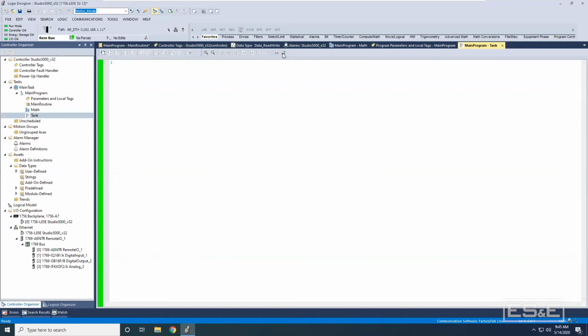But the other thing I really want to highlight is you have the ability to come up to here and you can see this toggle inline view or value display. So we're going to turn that on. I would always recommend adding that. What this does is it now allows you to see the values of the tags as you are building your code and it is executing. You never could do this previously, and it is an excellent improvement because now you can help diagnose and troubleshoot what is happening because the tags actually show you real values.